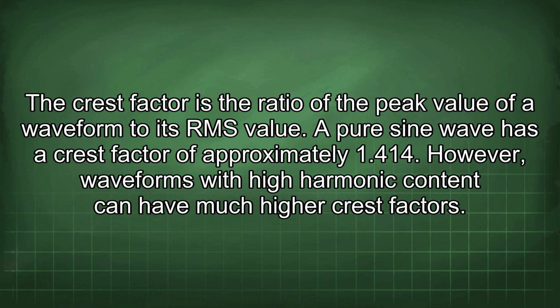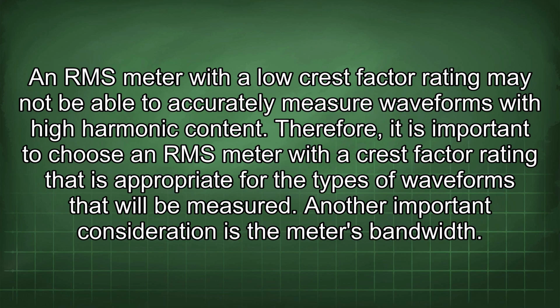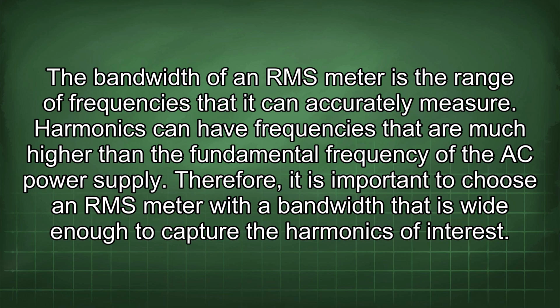However, waveforms with high harmonic content can have much higher crest factors. An RMS meter with a low crest factor rating may not be able to accurately measure waveforms with high harmonic content. Therefore, it is important to choose an RMS meter with a crest factor rating that is appropriate for the types of waveforms that will be measured. Another important consideration is the meter's bandwidth. The bandwidth of an RMS meter is the range of frequencies that it can accurately measure. Harmonics can have frequencies that are much higher than the fundamental frequency of the AC power supply. Therefore, it is important to choose an RMS meter with a bandwidth that is wide enough to capture the harmonics of interest.